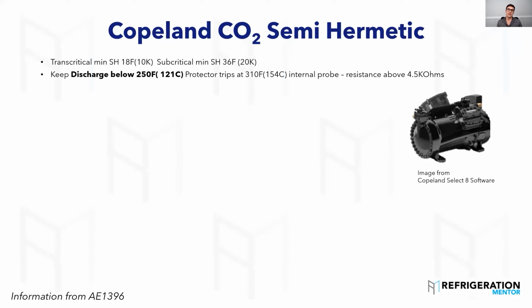For the semi-hermetic, you want to keep the discharge below 250, 121C. We saw Bitzer said 284, I believe it was 140C. And you want to make sure you're keeping it below that, because when you start to get higher, it starts to cause more wear, more heat, and more damage. The protector on this one will trip off at 310. There's an internal probe there, so you can check that. Use your meter, get it out, and check the sensors. Bitzer has the same thing. They have internal PTC sensors inside the compressor, so when your temperature gets too high, it'll stop the compressor to protect it.